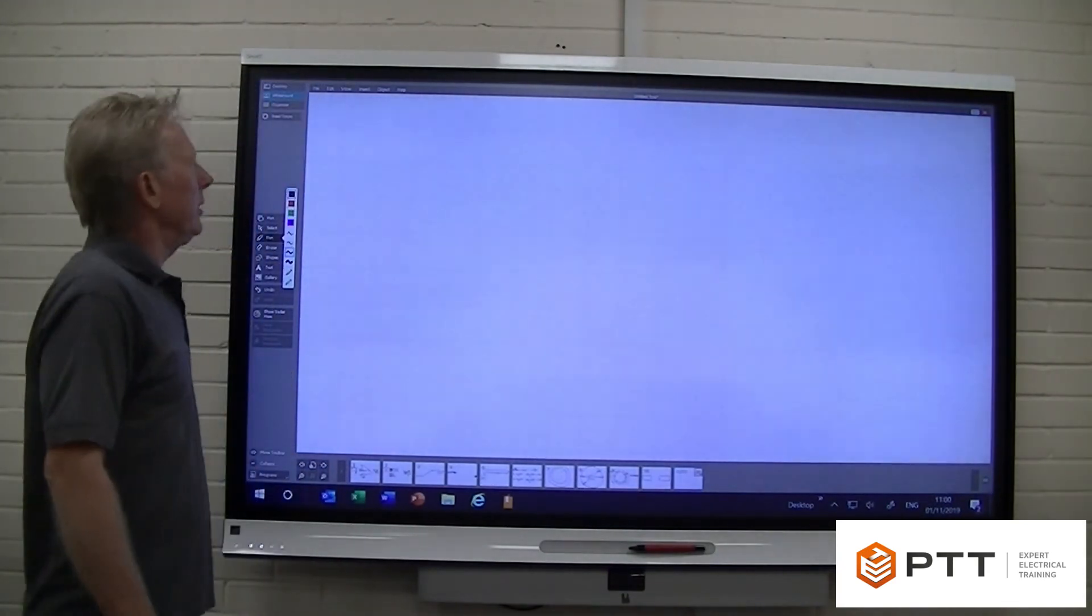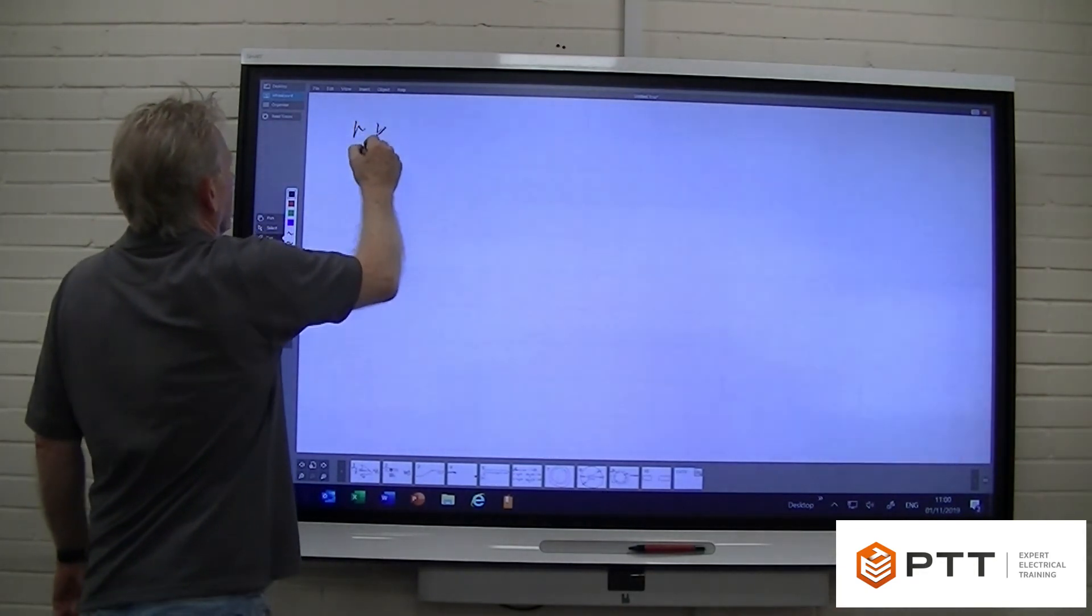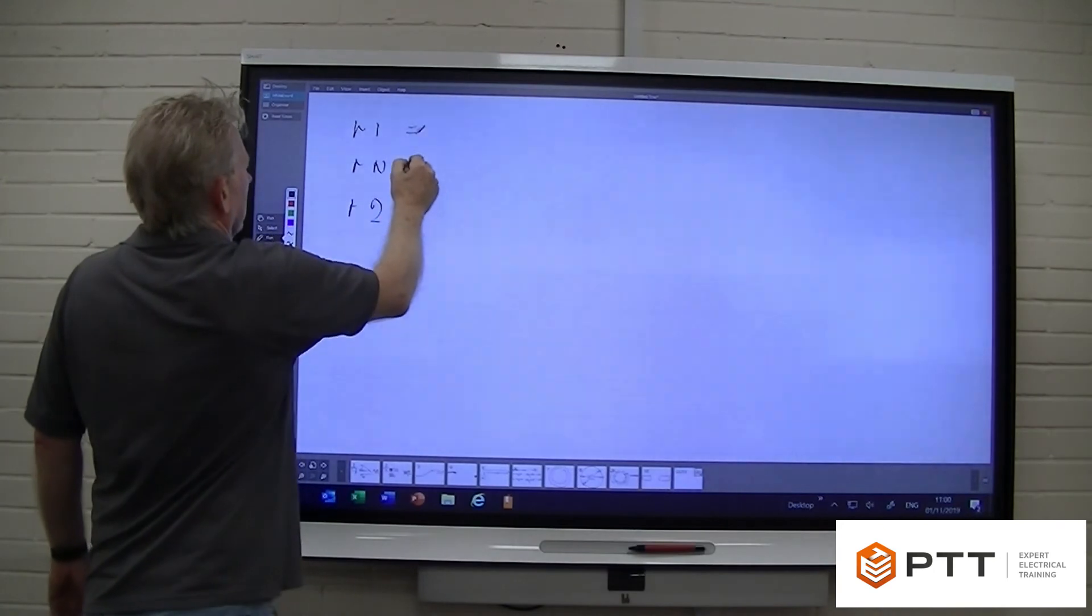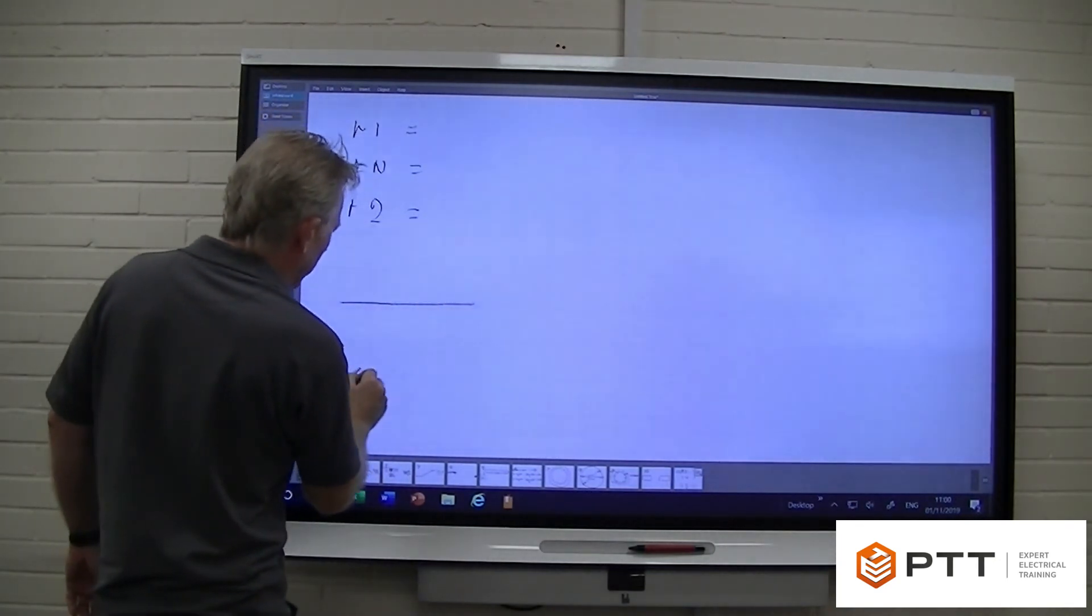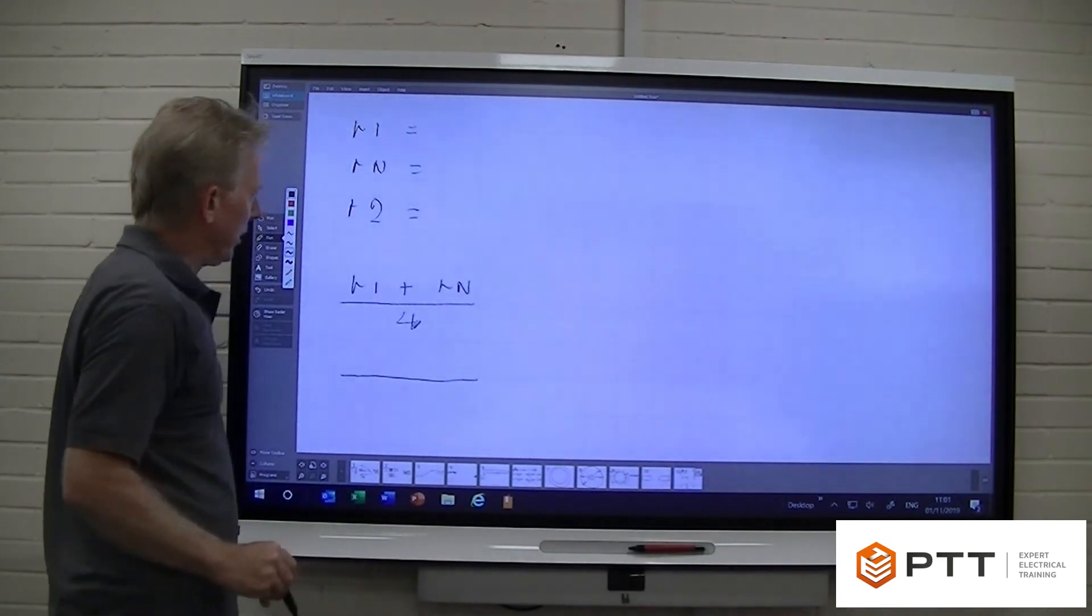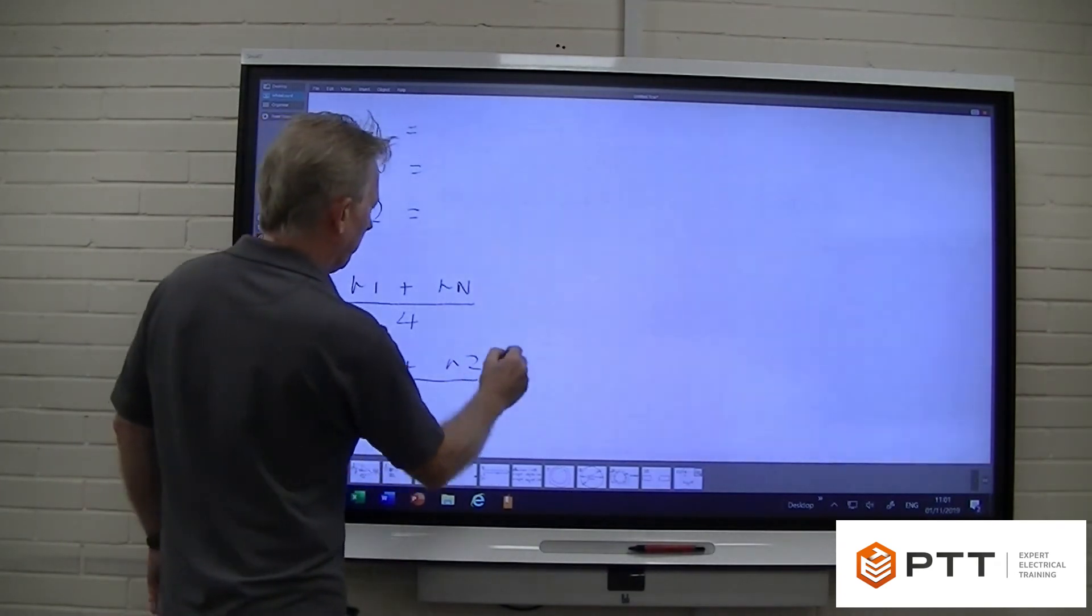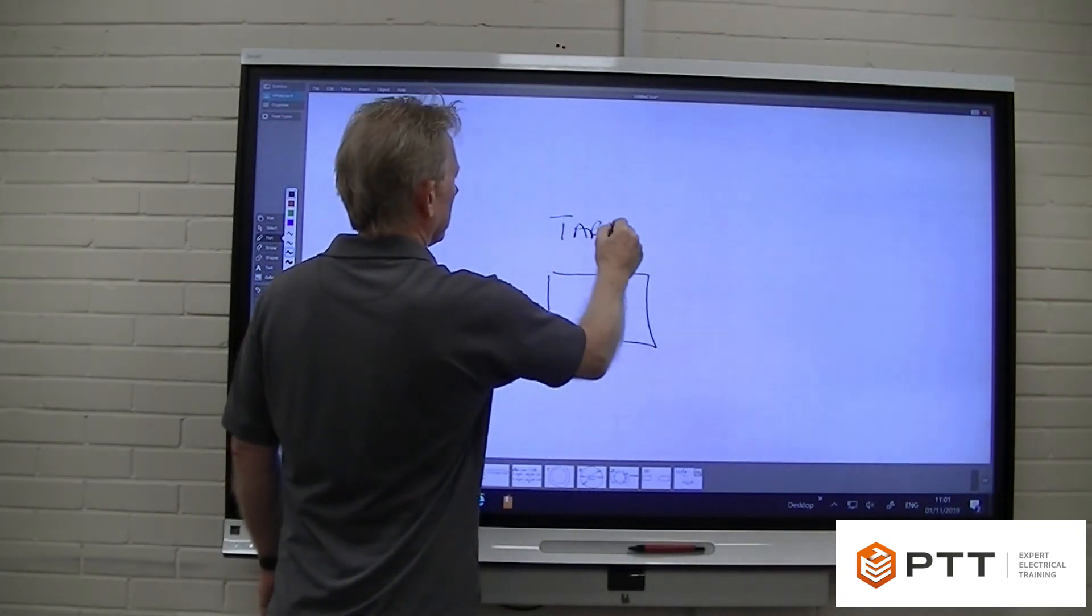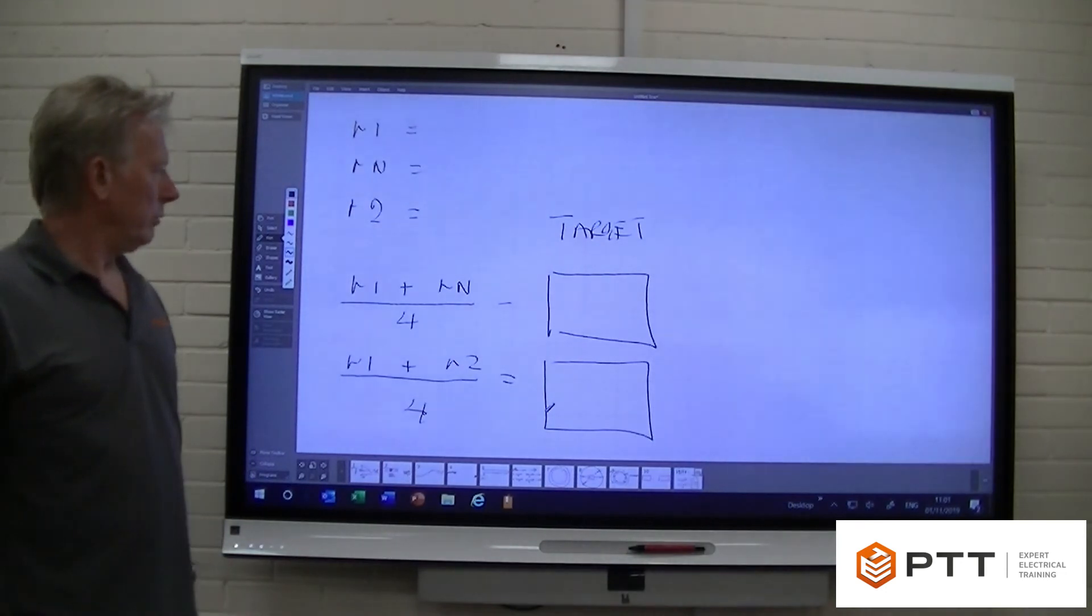What we teach here at PTT to help our students out is we get them to write this down every single time. It's called a pro forma. So we write down little r1, little rn, and little r2. We put an equal sign which just gives them somewhere to record the figures. We write down our two little equations: little r1 plus little rn over 4, and little r1 plus little r2 over 4. And that actually equals our target figure. And we're putting these boxes here just so that there's somewhere for people to record their results.